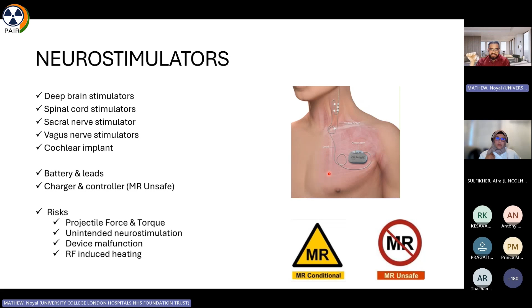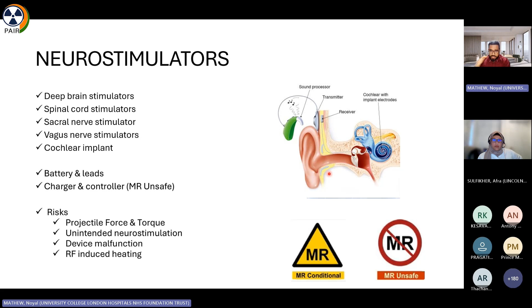MRI unsafe. You cannot permit that. The controller is normally patient held, like a phone, and there is the charger. And this is what it looks like. So the device is that which is sited on the patient. The leads are sometimes not visible, considering they go into the body. The remote control and charger cannot be permitted into the room at any point of time.